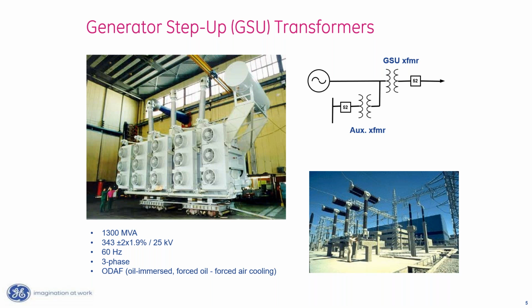The other job that a generator transformer performs is that it typically has a delta to Y conversion. And the delta connected windings are typically wired to the generator side of the GSU rather than the high voltage transmission side. What that does for us is that it blocks the zero sequence current from the generator.